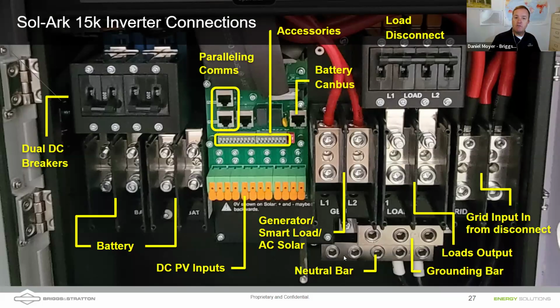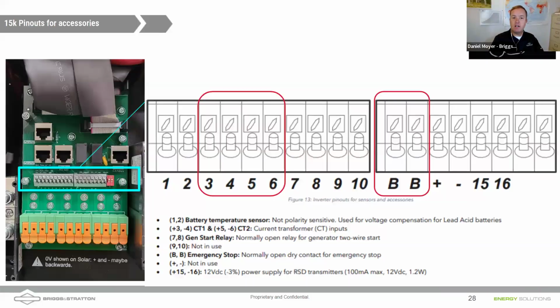In that 18K, it's now vertical. These are the accessory pinouts. This is where our battery communication is going to be. Parallel comms is if we're going to have multiple inverters, battery inputs, and the battery breakers are on the left-hand side. If we're going to be wiring those CTs, they go into pins 3, 4, 5, 6. Our rapid shutdown button is going to be on BB.